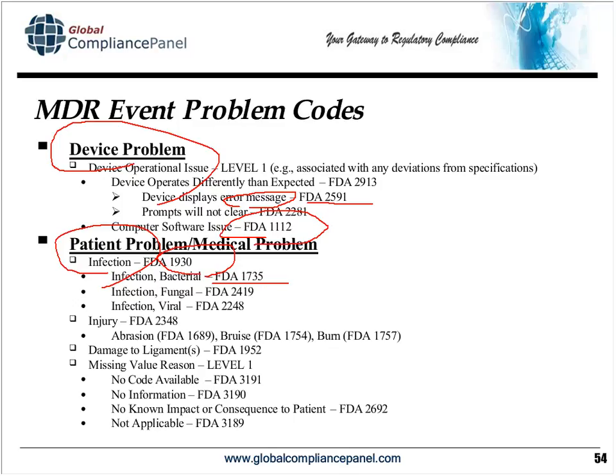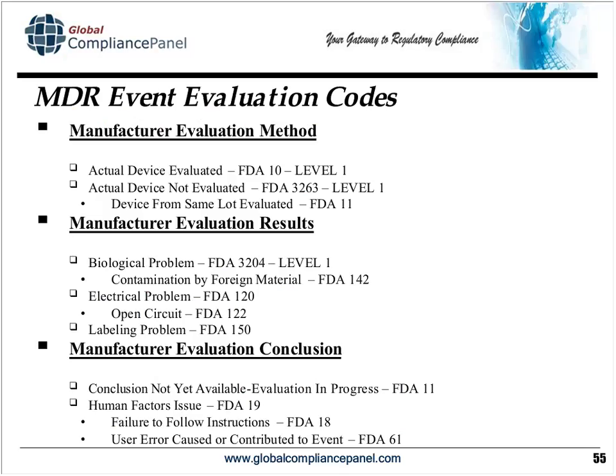This problem code needs to be used when a user facility files their report to the manufacturer or FDA. The medical device evaluation code is for manufacturers. Again, I recommend you use this term because it can describe the event very well. Manufacturer evaluation: what method, how did you evaluate an event? Well, we used the actual device evaluated. However, we were not able to recover the actual device of the incident, and then your actual device not evaluated, FDA 3263.